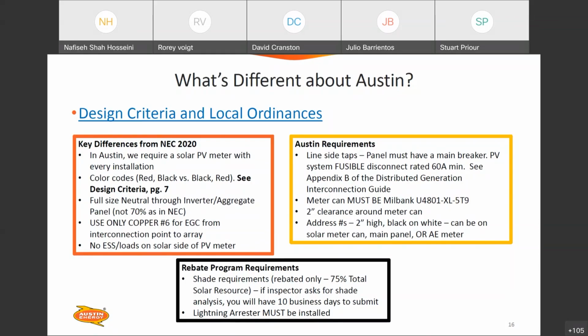Line side taps: any panels with line side taps must have a main breaker. What you're doing with a line side tap is creating a separate service disconnecting means, so you need overcurrent protection as close as practical to where you made that tap. There are diagrams in Appendix B of the interconnection guide that help explain this.